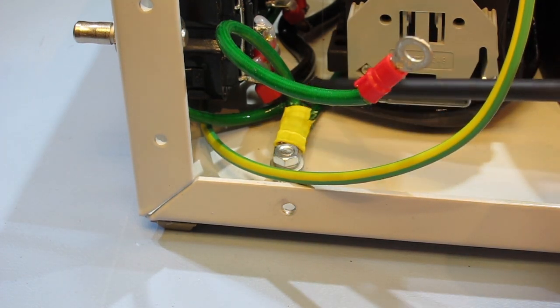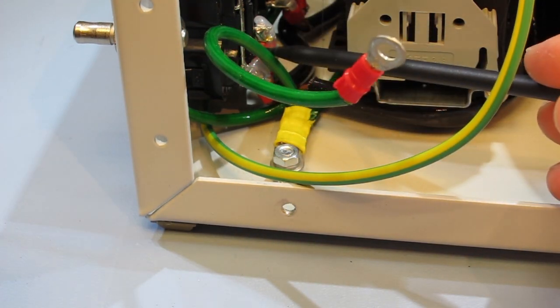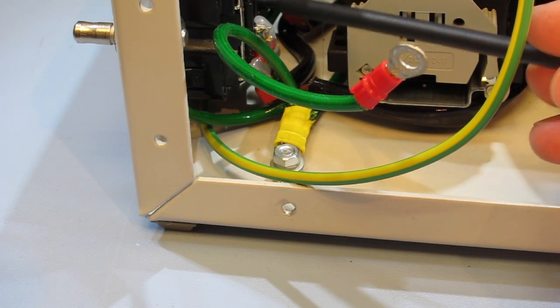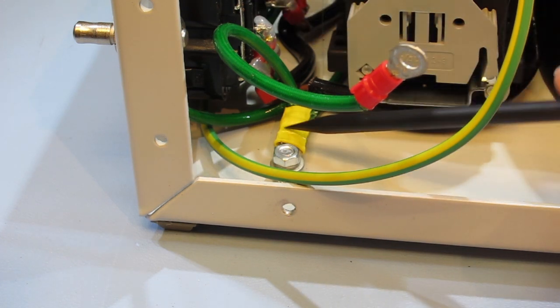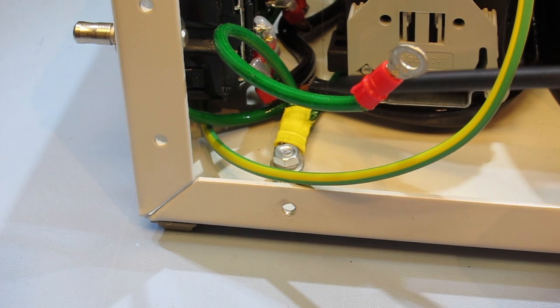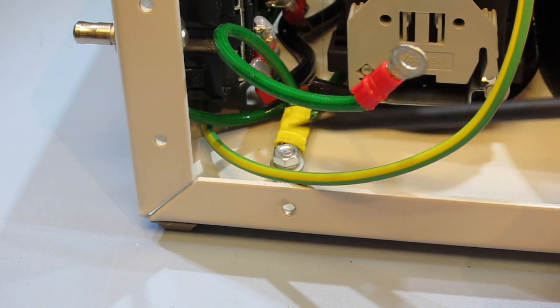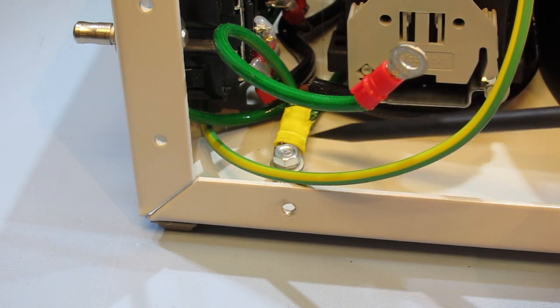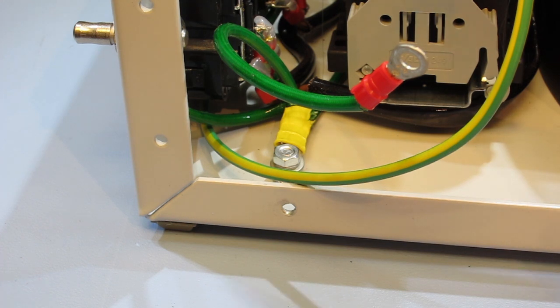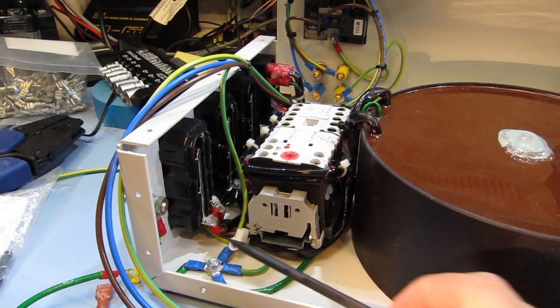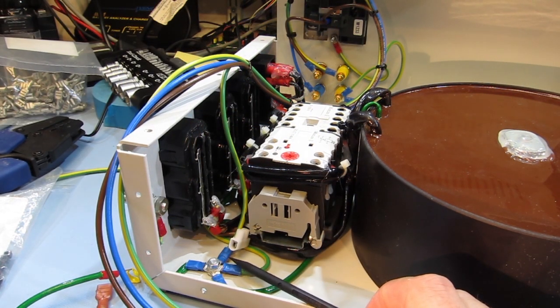We'll disconnect the earth connection that did come from these IEC connectors from here, and then also we'll take a new wire from this point up to the top cover onto the banana jack that we can then link in if we do want the outlets to be earthed.